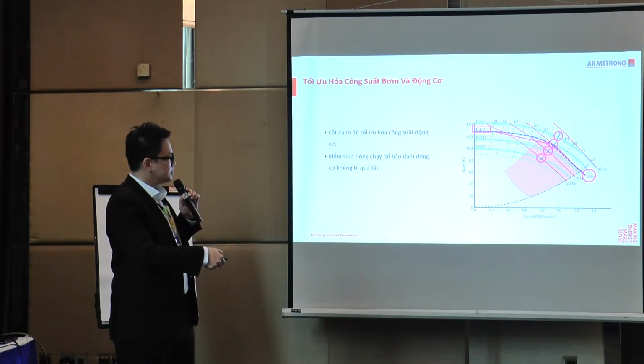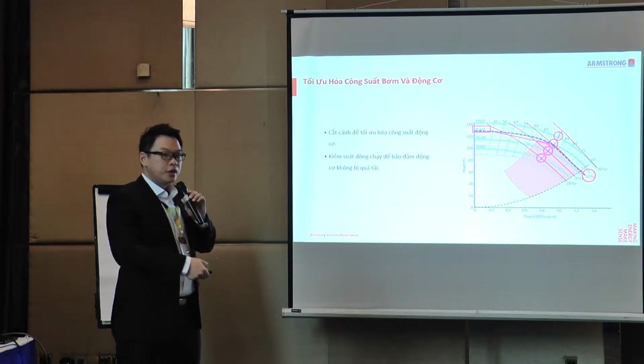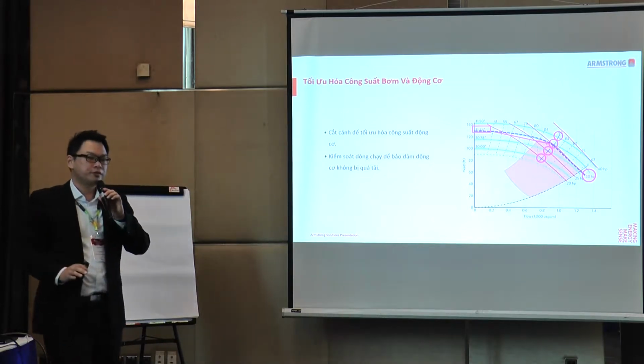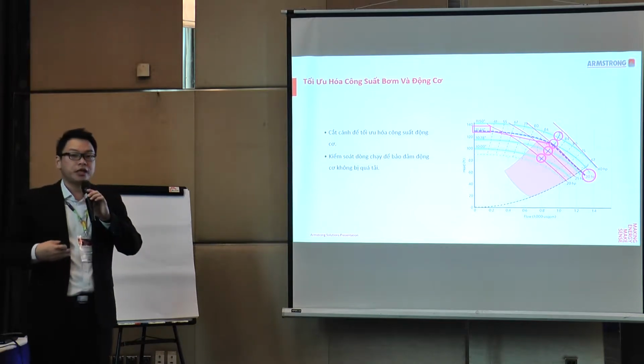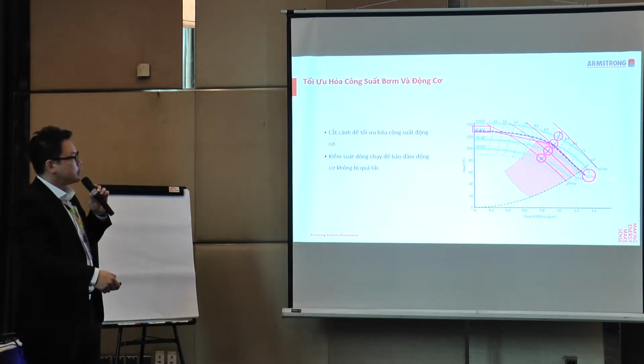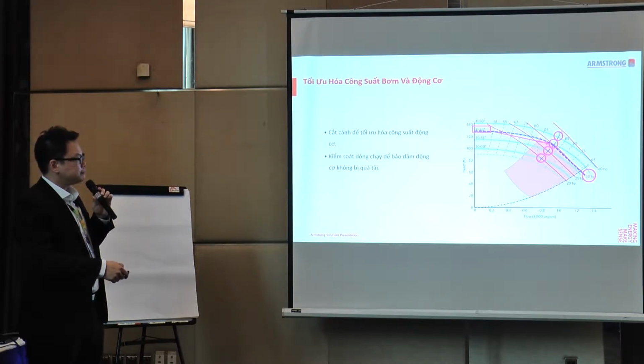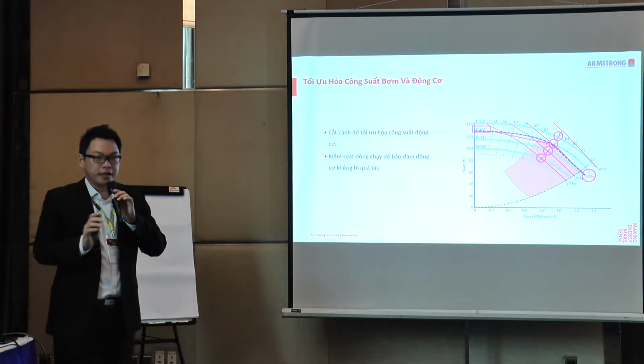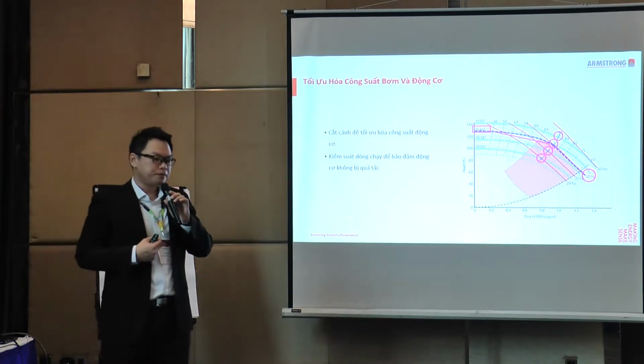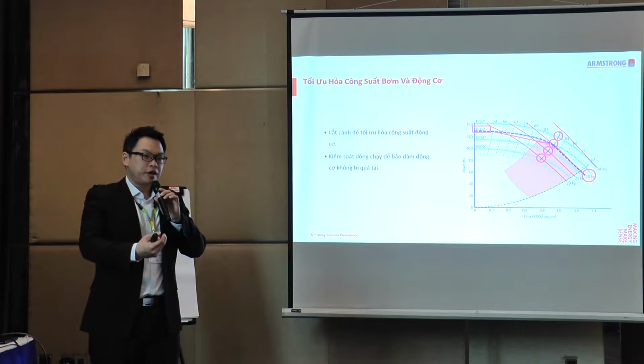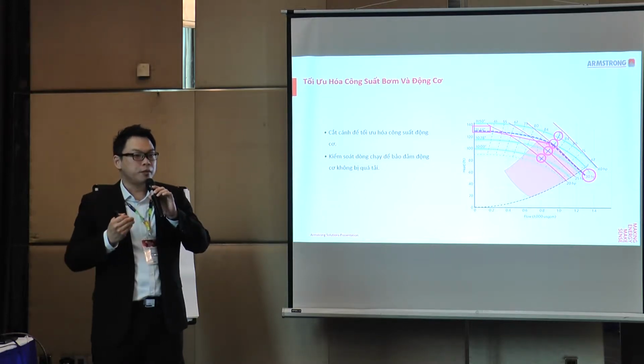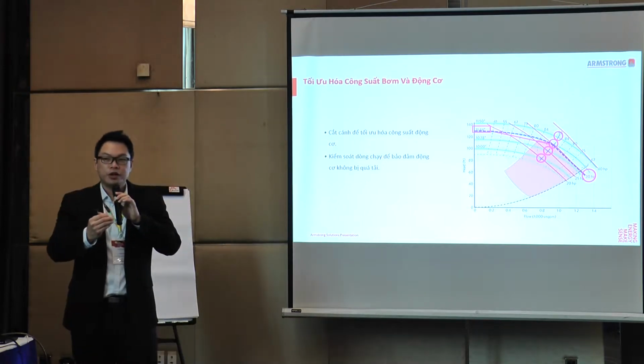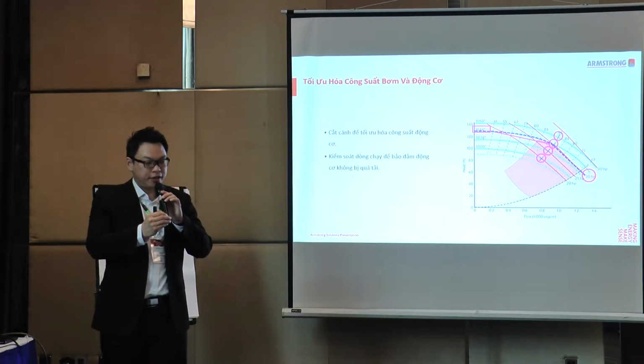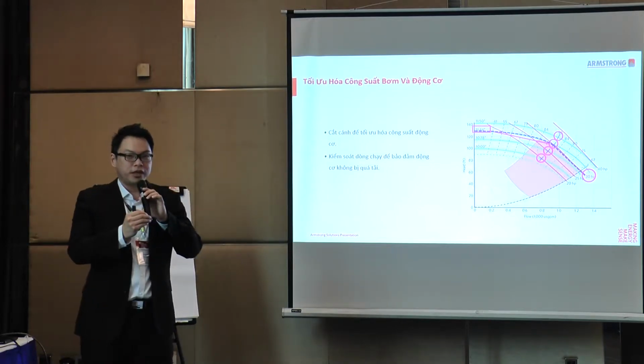the 25 horsepower, because your end of curve will exceed the motor horsepower curve. So we have to go for the next size, which is 30 horsepower. You will realize that the 30 horsepower here is intersecting the 11.44 inches impeller size. So for us at Armstrong, since we are already going to use the 30 horsepower motor, why don't we optimize the impeller trim? Instead of using 10.78 inches, why don't we use 11.44 inches?